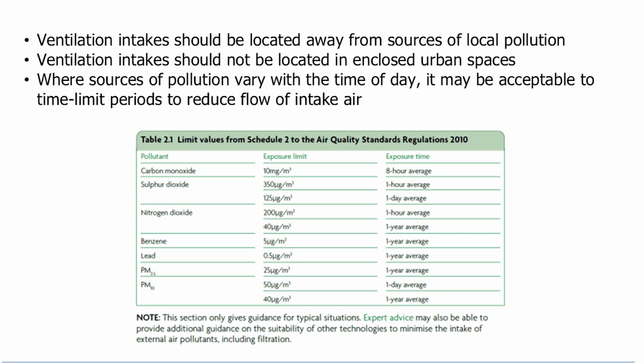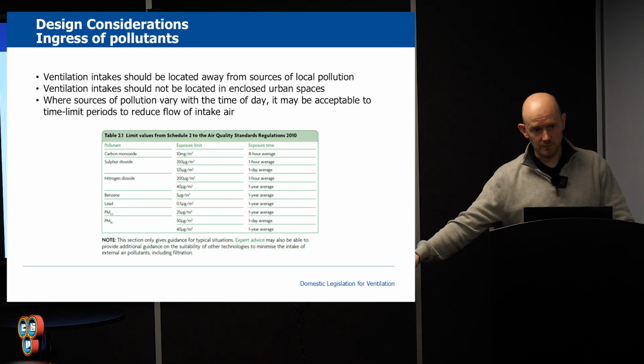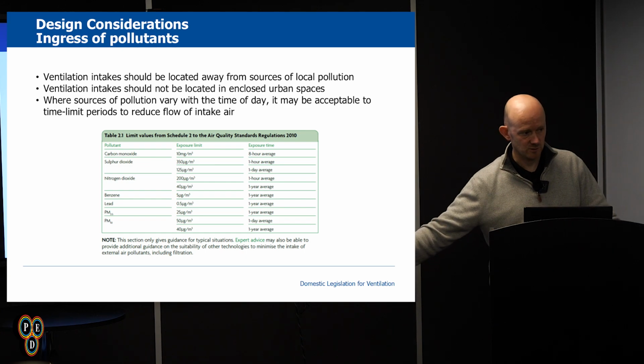If you get asked to supplement the filtration system with further filtration, as in, you'll hear the word NOx filtration. I don't know if you've ever heard of NOx filtration. It's to take out petrols and gases and diesels out of the air. So if you've got a building set of flats on a busy high street, they will want NOx filtration in the system. Be very careful. That definitely has to be designed, because yet again the filters are massive. They're in addition to the filters that come in the unit, so it's two sets of filters.